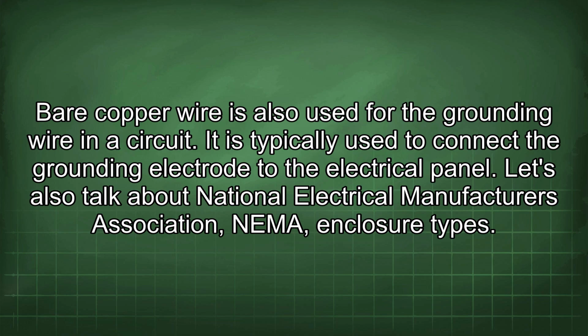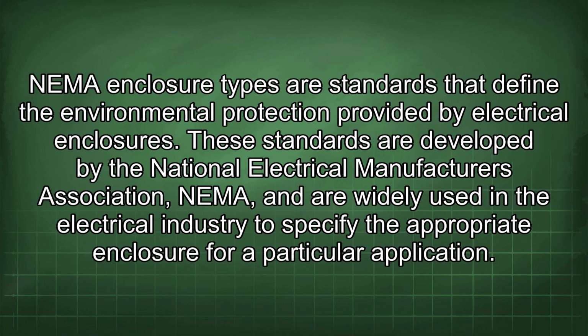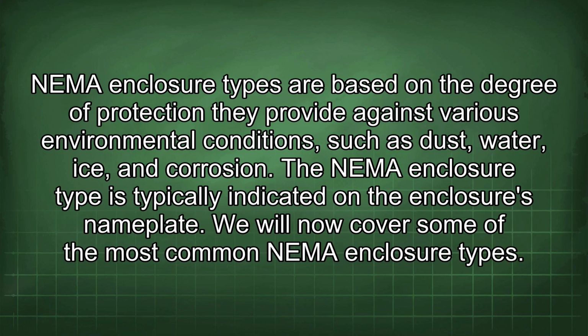Let's also talk about National Electrical Manufacturers Association (NEMA) enclosure types. NEMA enclosure types are standards that define the environmental protection provided by electrical enclosures. These standards are developed by the National Electrical Manufacturers Association (NEMA) and are widely used in the electrical industry to specify the appropriate enclosure for a particular application. NEMA enclosure types are based on the degree of protection they provide against various environmental conditions such as dust, water, ice, and corrosion. The NEMA enclosure type is typically indicated on the enclosure's nameplate.